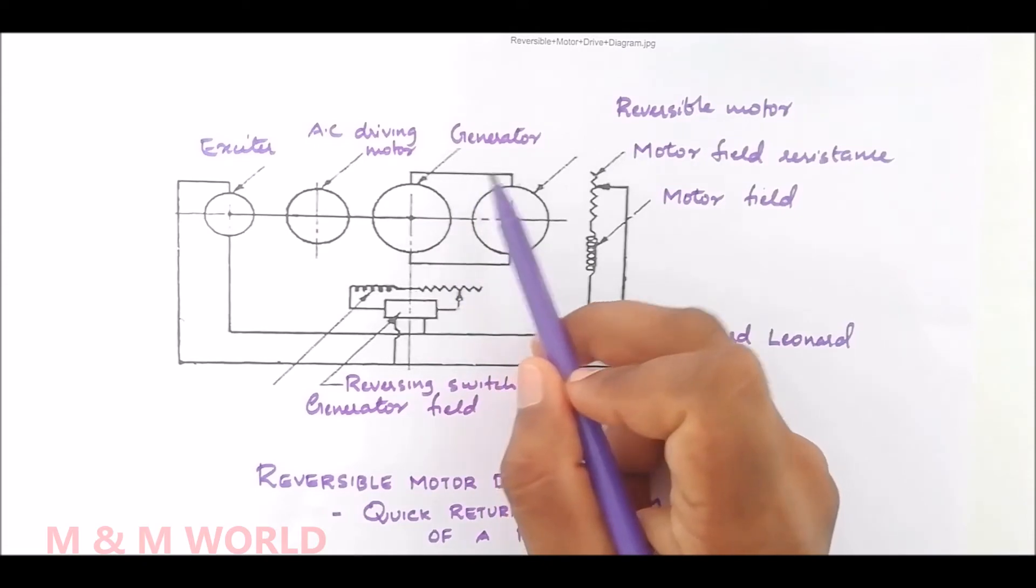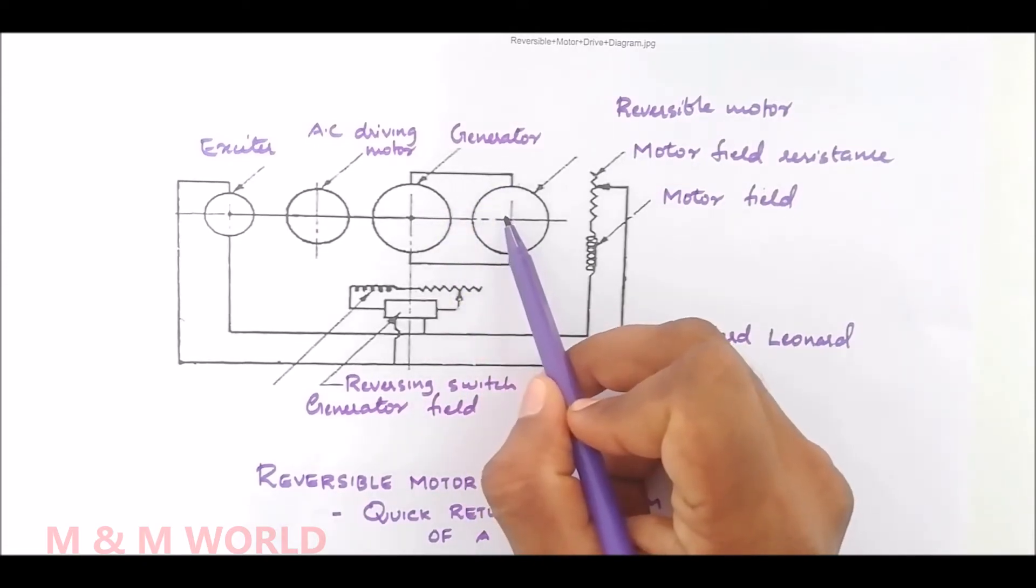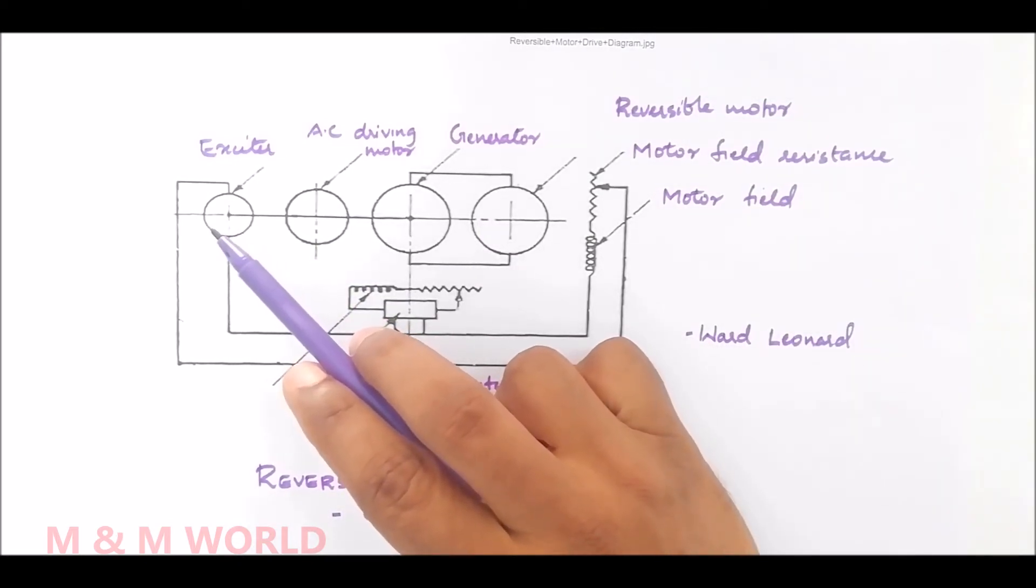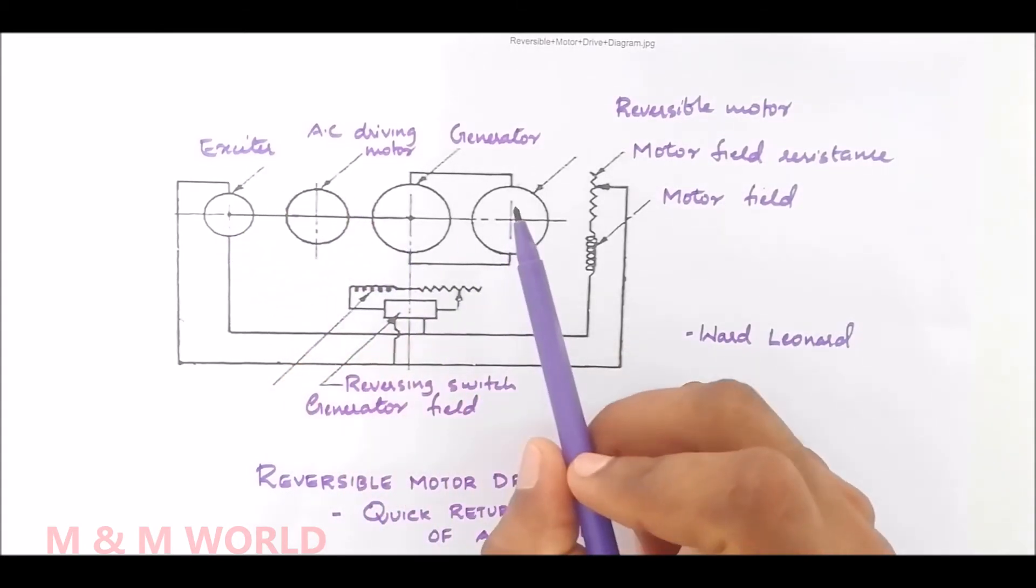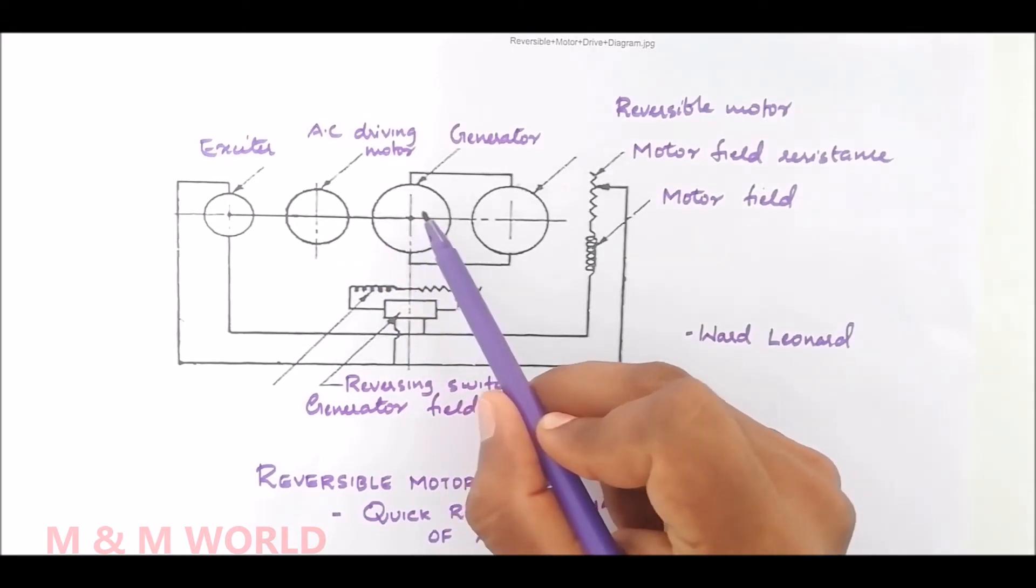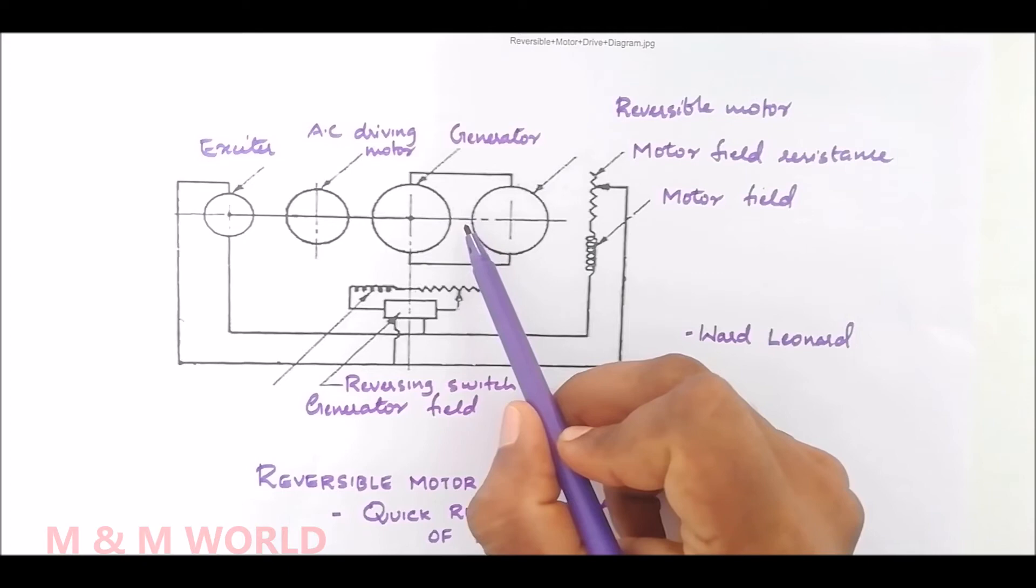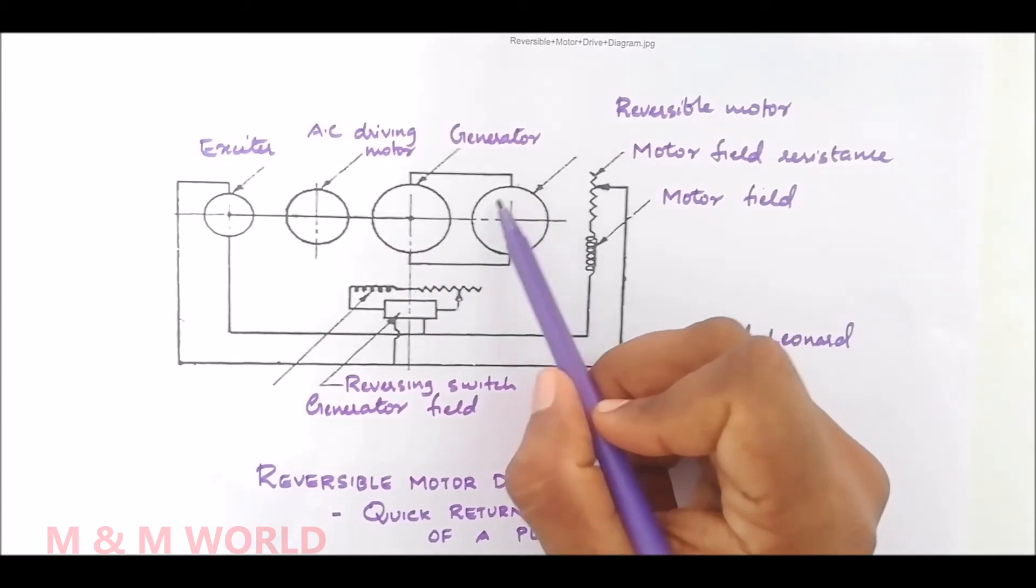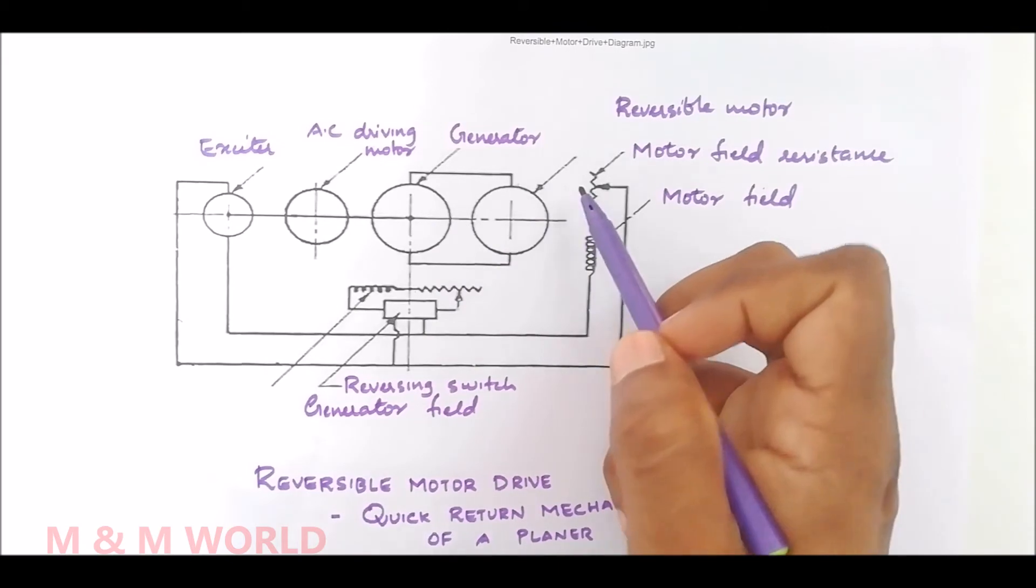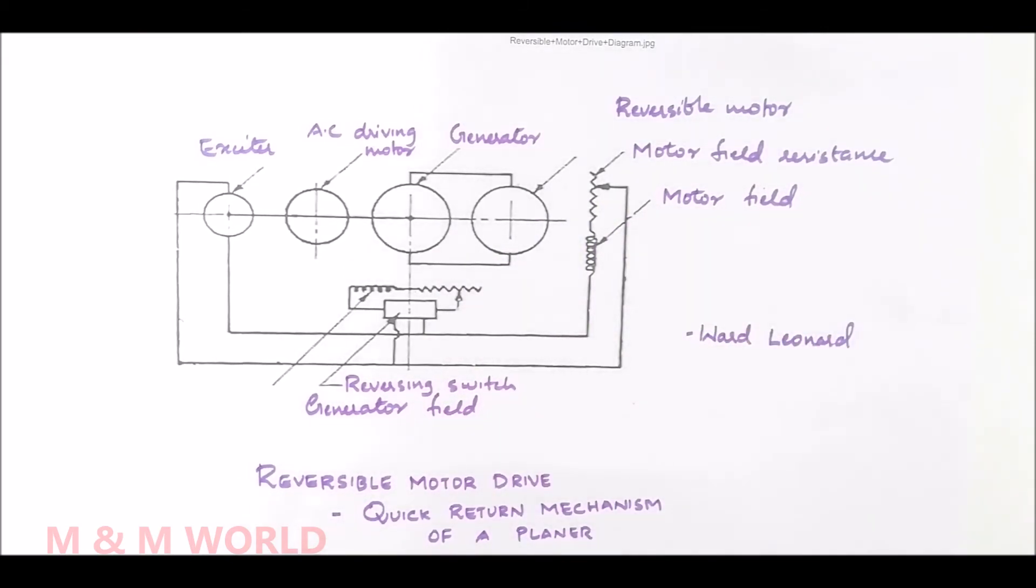The field current for the generator and the reversible motor is obtained from the exciter. To start the machine, the motor generator set is started and the generator supplies power to the reversible motor which causes the table of the planer to move in a particular direction.